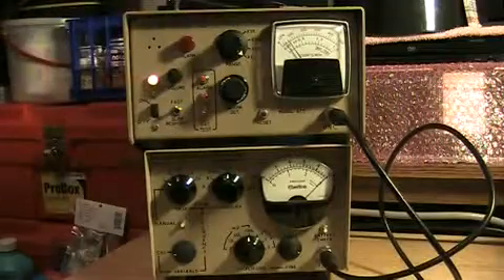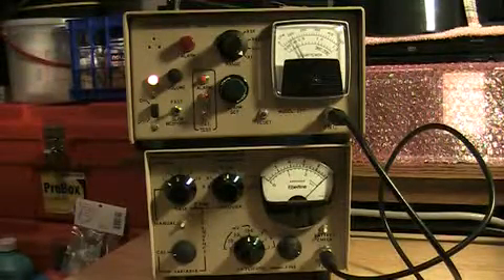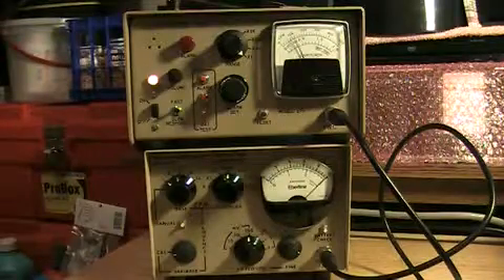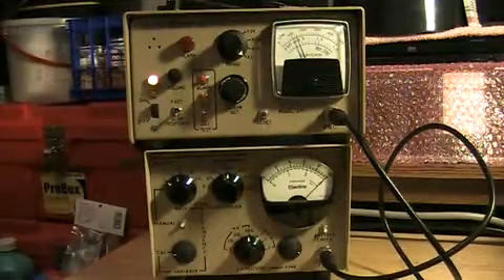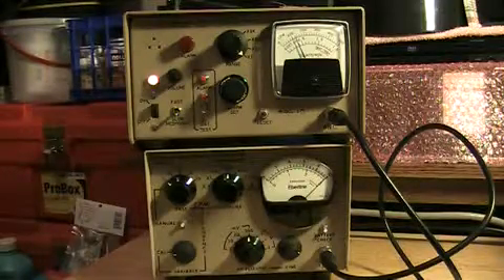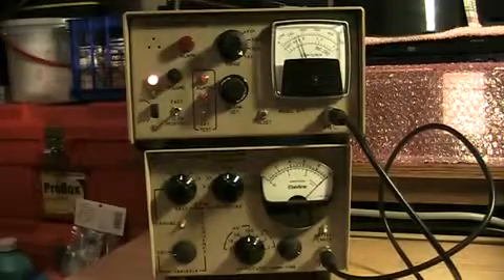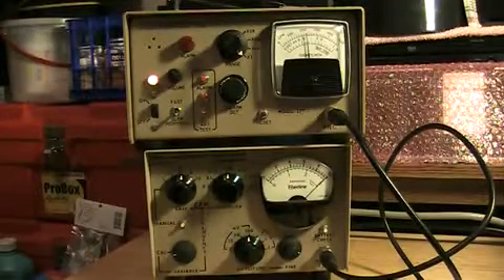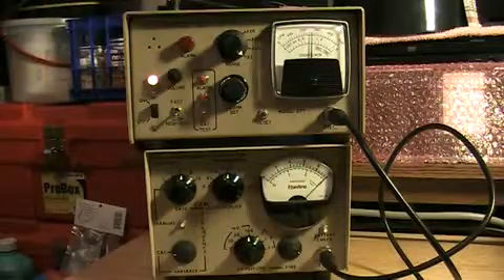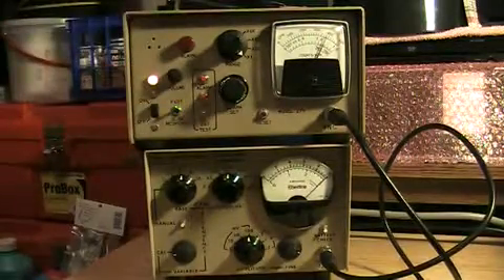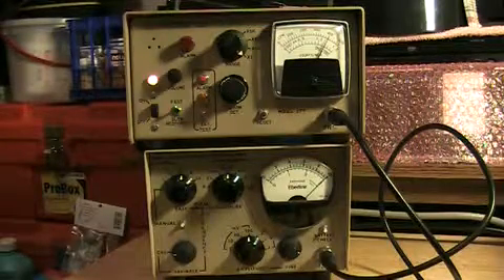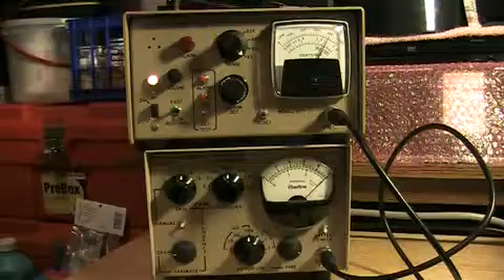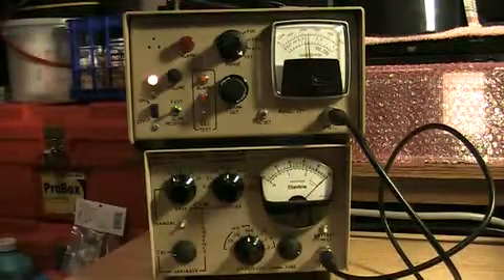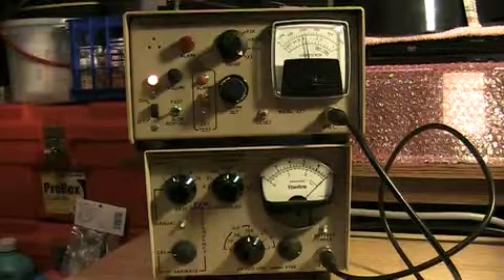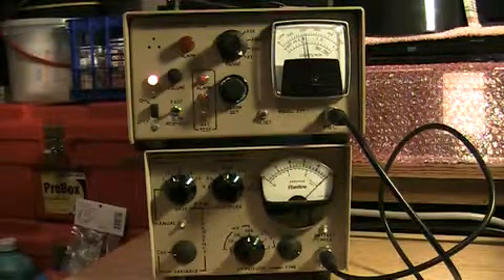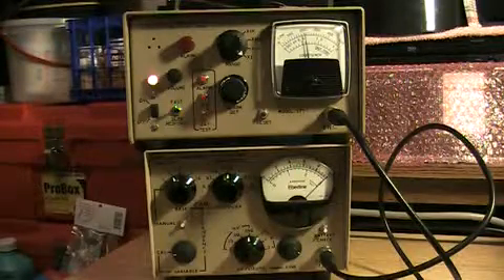Go down to ×1. And due to the meter bounce here, it's harder to get this really zeroed in. If I go slow, it'll level it out. Go up to 4. Let me go up to fast. Get some meter bounce. That's right at 400 counts per minute. And again here at the lower counts it starts bouncing. There's 200 counts per minute.